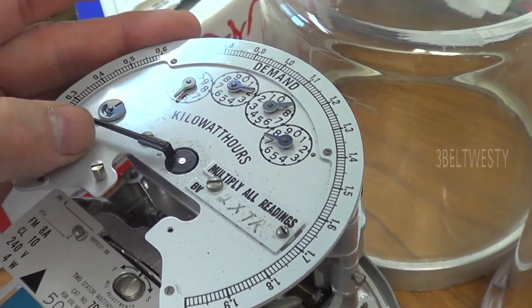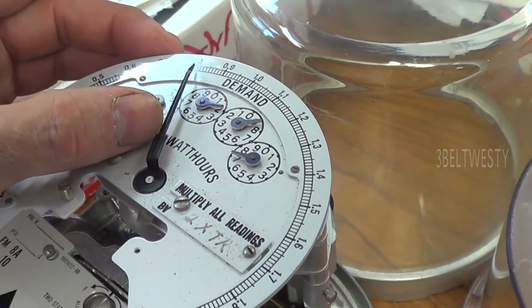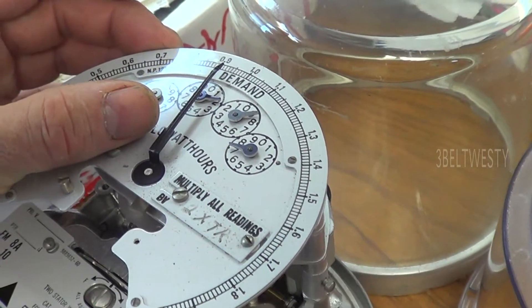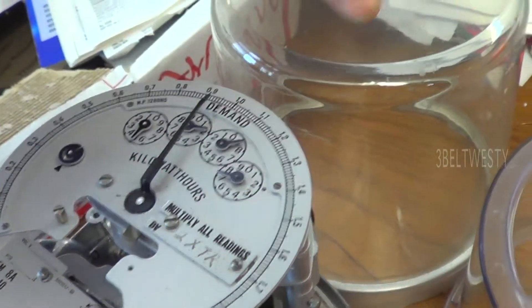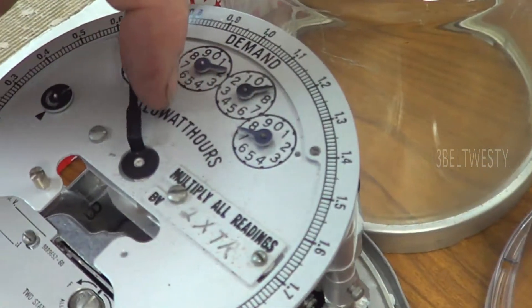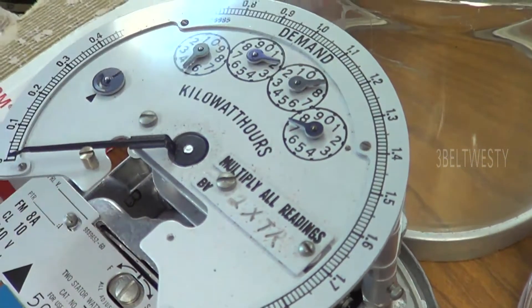And then when it's running the peak demand will go up here like this over the 15 to 30 minute period depending how it's programmed or set up. And then once a month utility worker will go ahead and turn this down and it'll move the back down here to zero.